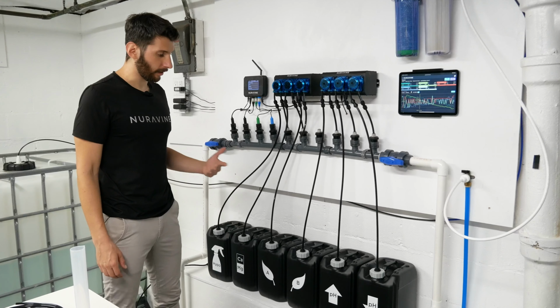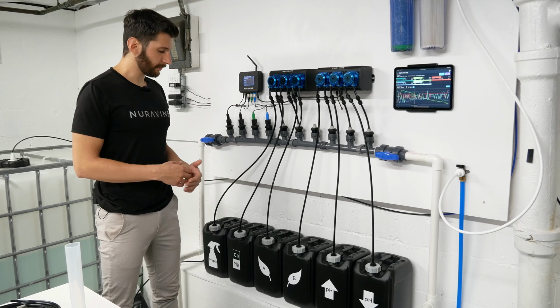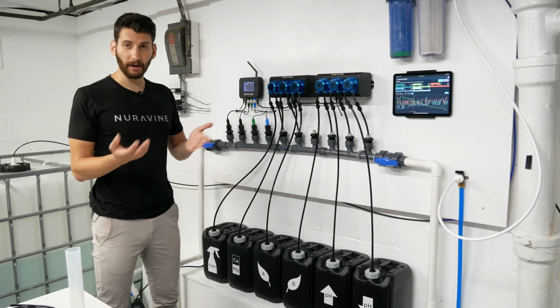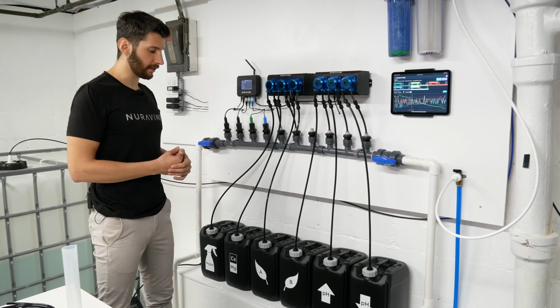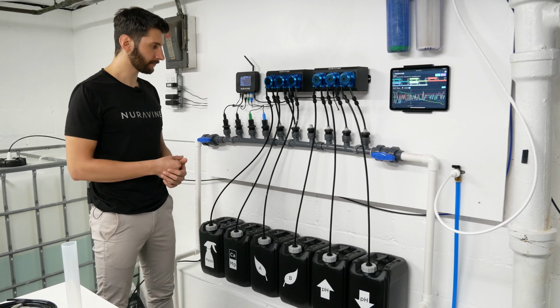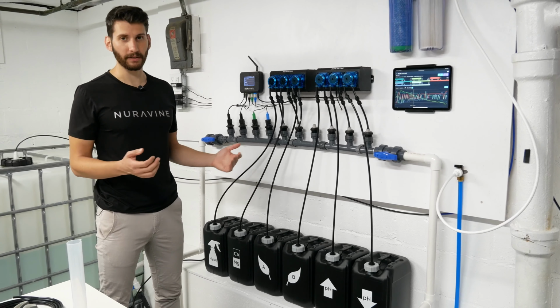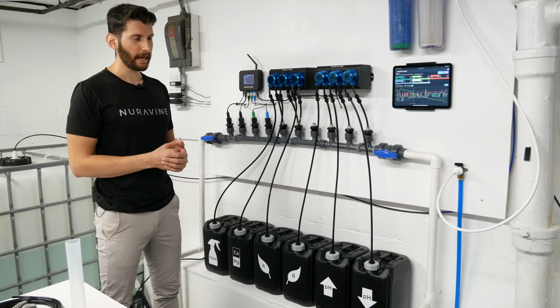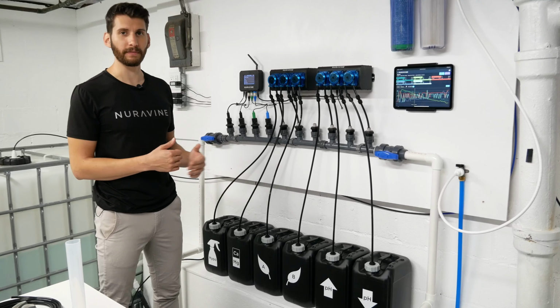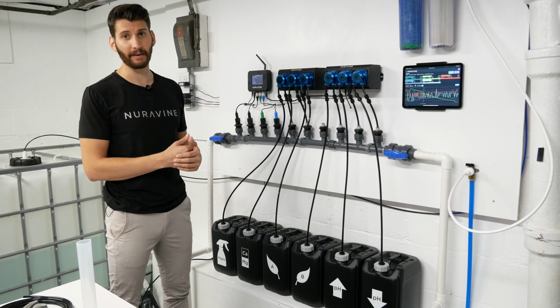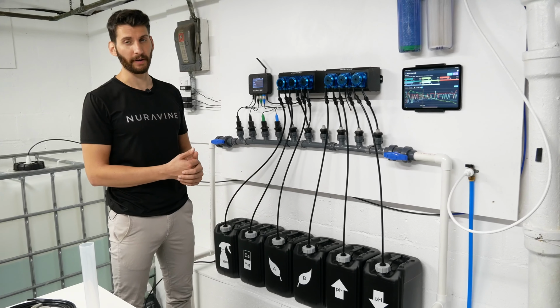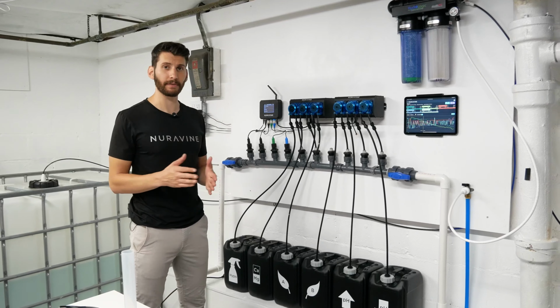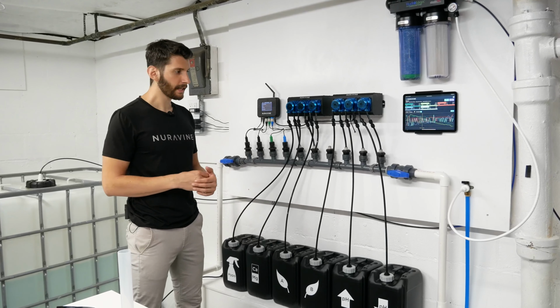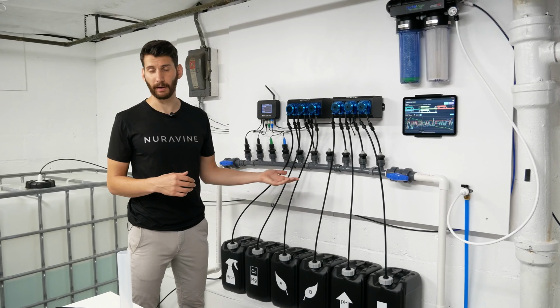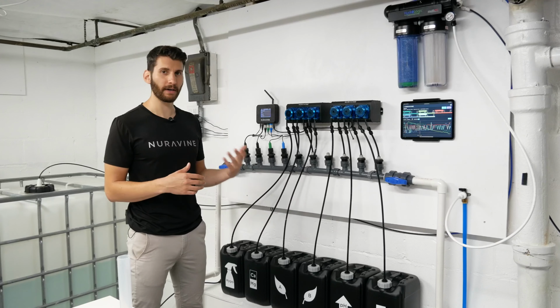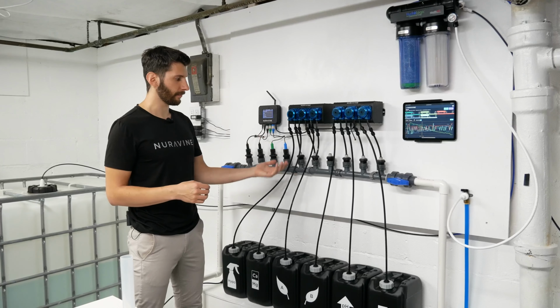Also, if you're using pumps or bottles that are far away or from a different elevation, then you may have more issues priming than normal. The pumps are tested to prime from over 200 feet and can pull from about 20 feet of elevation, but when you're pulling from a higher elevation, it is going to reduce the flow rate. Additionally, if you're working with nutrients of different viscosities, it's also going to affect the speed at which it pumps and primes. So make sure you're taking all those variables into account when priming your pumps.